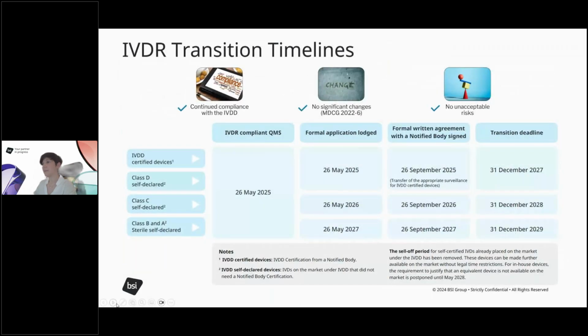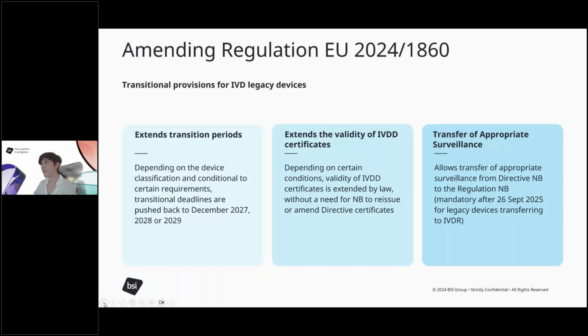Talking about these elements one by one, starting with the transitional provisions for IVD legacy devices. The amending regulation extends the transition periods. Depending on the device classification and conditional on certain requirements, the transitional deadlines are pushed back to December 2027, 2028, or 2029. The amending regulation also extends the validity of IVDD certificates. Depending on certain conditions, the validity of the IVDD certificate is extended by law without a need for the notified body to reissue or amend the directive certificates.